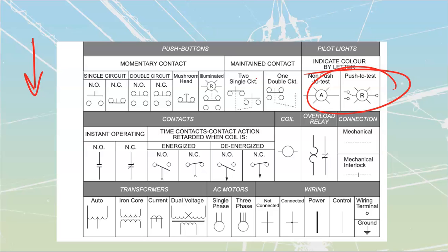And I'd go there and the thing would be working. They'd be like, but the light's not on. So I'd pull out the light bulb and replace the little incandescent light bulb. We have that less commonly at this point. We do still push to test, but it's less commonly needed now because we have such long lifespans.